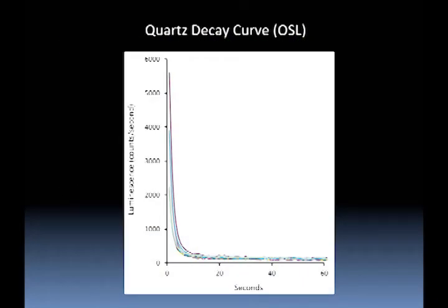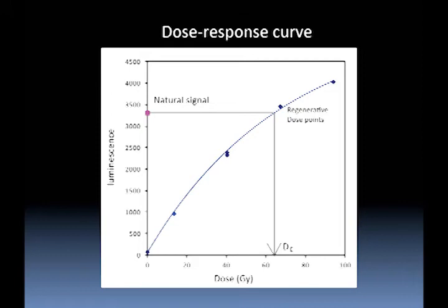This is what the luminescence signal looks like from a sample of quartz. So we have turned on the stimulating light source right at this exact instant, and the sample luminesces and decays to a background. And there's actually, I think, 14 different measurements here to go through that measurement cycle. To measure different steps, we need to determine the characteristics of the luminescence. And then the signal is generated as the first 4 data points on the signal decay curve minus the background. So every sample will have a certain thermal background. The instrument has a background. We subtract that out. This is what the single aliquot regenerative cycle measurement cycle looks like, what we do.